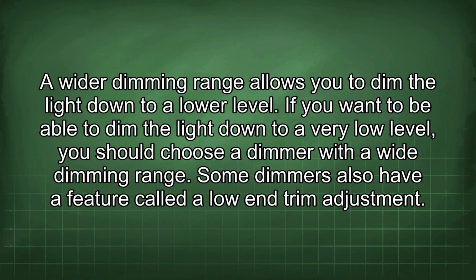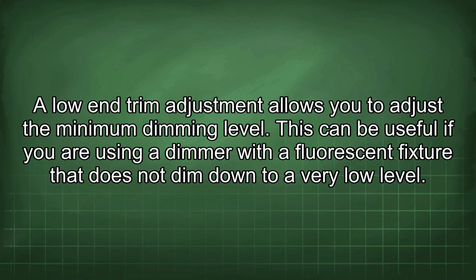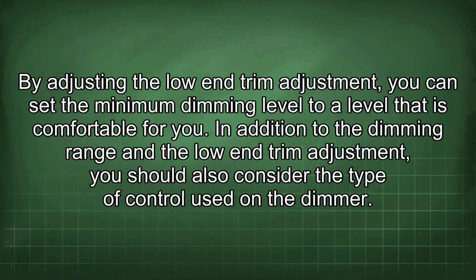Some dimmers also have a feature called a low-end trim adjustment. A low-end trim adjustment allows you to adjust the minimum dimming level. This can be useful if you are using a dimmer with a fluorescent fixture that does not dim down to a very low level. By adjusting the low-end trim adjustment, you can set the minimum dimming level to a level that is comfortable for you.